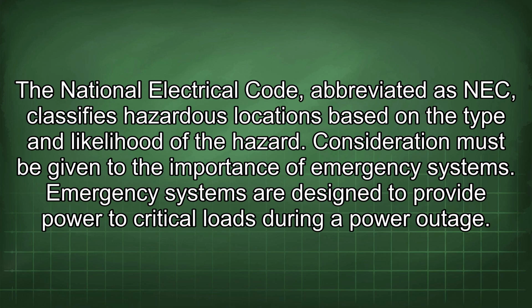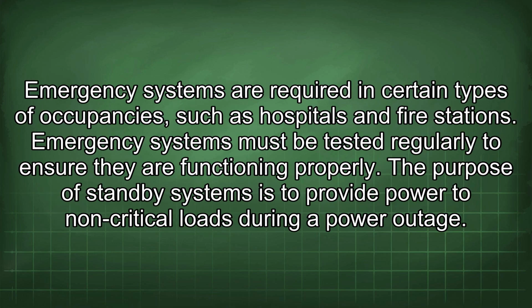Consideration must be given to the importance of emergency systems. Emergency systems are designed to provide power to critical loads during a power outage. Emergency systems are required in certain types of occupancies, such as hospitals and fire stations. Emergency systems must be tested regularly to ensure they are functioning properly.